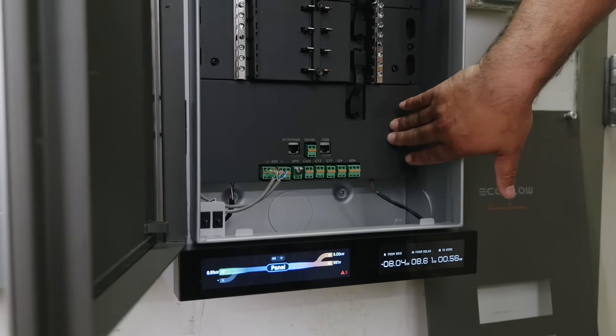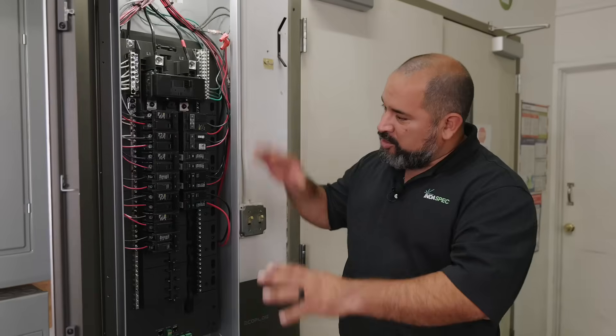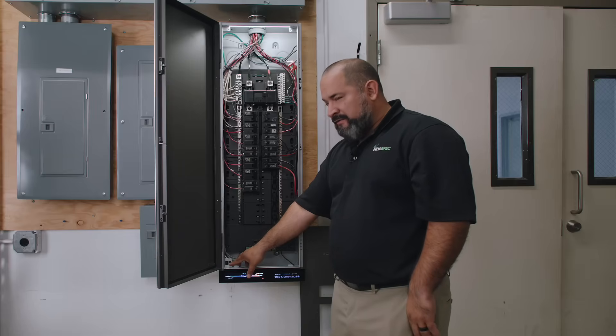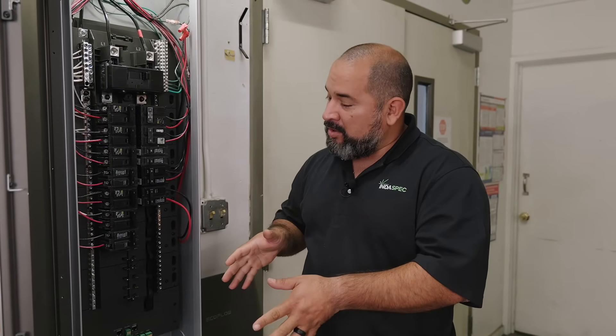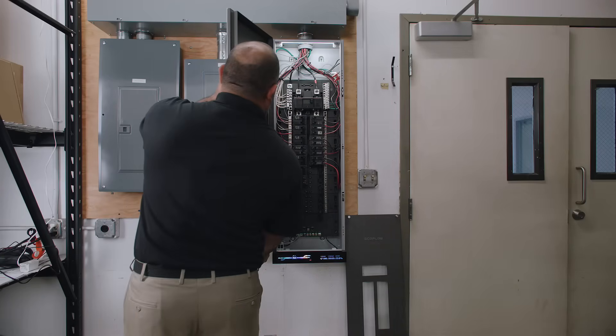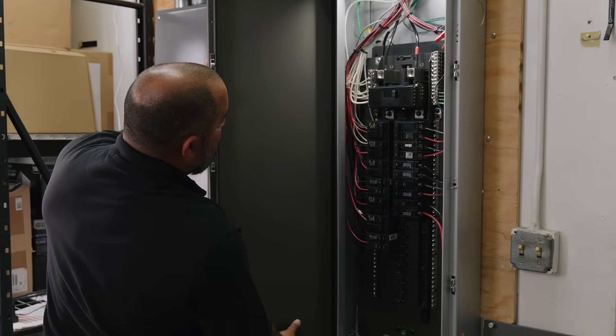The computer module provides ESS integration, smart stop, communications, CT, and battery integration. True to the EcoFlow ecosystem, the system is extremely safe — it has a fail-safe that automatically disconnects power to the panel if the dead front is removed, ensuring you're never working in a hot environment. The door works from both right and left installation orientations and is very easy to install and uninstall for unobstructed access during the installation process.